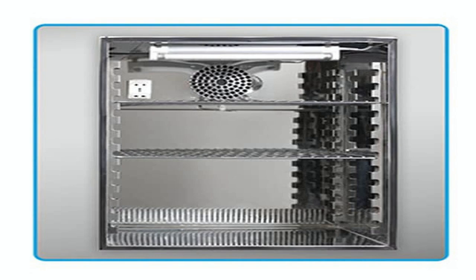65L is generous. You can fit a handful of standard 100mm Petri dishes, a few T75 flasks, or even a small rack of microplates. But that space also means you have to be mindful of airflow inside. The Mytemp uses a forced air system, so you'll notice a gentle breeze when the door is open. If your protocol involves very delicate, loosely attached cultures, you might have to add a secondary lid or use a more closed container to avoid drying out. That's a nuance you don't see on the spec sheet, but becomes clear once you start loading the unit with actual samples.